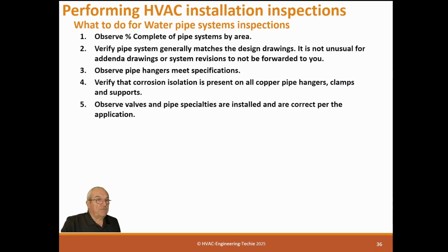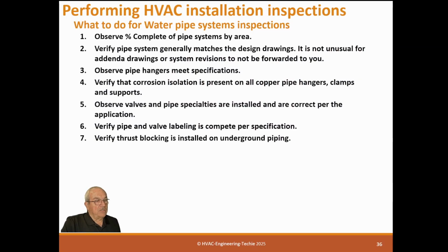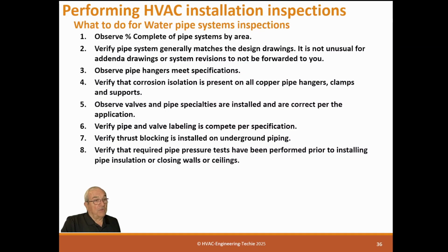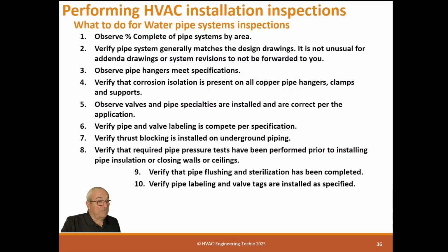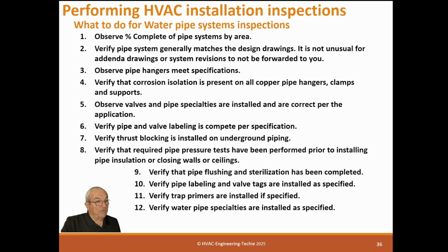Observe valves and pipe specialties are installed and are correct per the application. Verify pipe and valve labeling is complete per specification. Verify thrust blocking is installed on underground piping. Verify the required pipe pressure tests have been performed prior to installing pipe insulation or closing walls or ceilings. Verify that pipe flushing and sterilization have been completed. Verify pipe labeling and valve tags are installed as specified. Verify trap primers are installed as specified. Verify water pressure specialties or water pipe specialties are installed as specified.